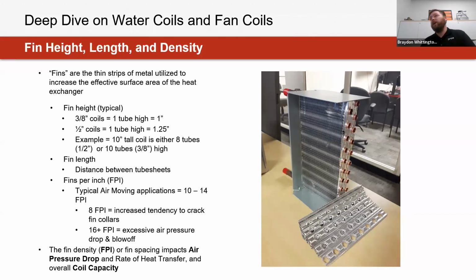So commonly, for air moving applications such as terminals, fan coils, and blower coils, typically this is within that 10 to 14 fins per inch range. The reason, as we discussed, is that if we were to get above that benchmark, we're going to see a lot of additional pressure that coil is going to add on our system or on that fan. And if we were to go below that threshold, let's say 8 or 6 or even below, that's where it gets more exposed to potential cracking at the coil or even as it's transported, because this is not as strong a material, especially as it's more spaced out. So you can only imagine trying to handle that in the field, with the potential of even damaging that coil as you're trying to install it into the ductwork of a system or as that product is being transported.